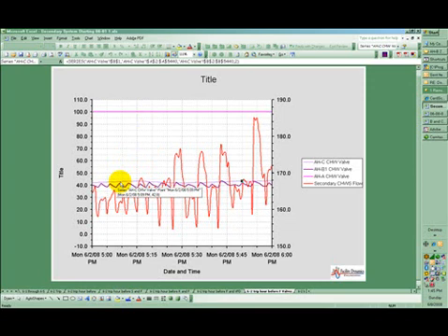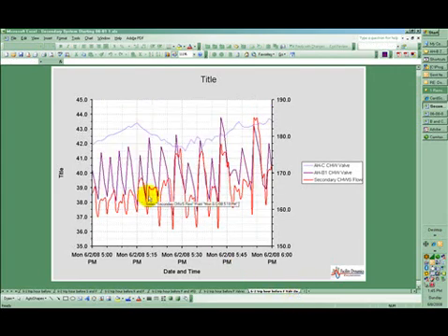But interestingly enough, the B valve showed an oscillation that sort of correlated fairly well with the flow. And so if I zoomed in on that and laid them on top of each other, you can see that there is a really strong correlation between what air handler B's valve is doing and the flow variations in the system. The C valve is wandering around a little bit, but not near as much as the B valve. The B valve's about four times, or once every 4 minutes. It's about 15 times an hour, and it's only like about a 3 or 4% change in output that's causing the flow to vary as much as 25%.